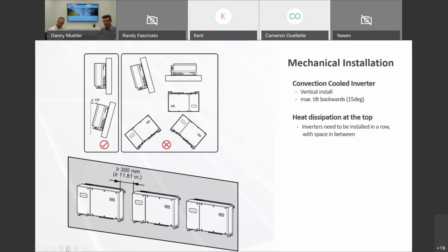When you have multiple inverters on a side or on a rack adjacent to the roof-mounted array, then you have to have a little gap between the inverters, which in this case Huawei specifies at roughly about a foot, to have enough space for radiation from that heatsink as well.